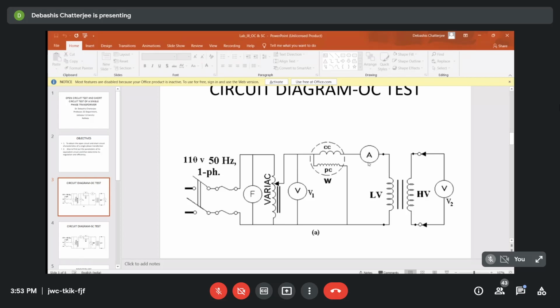So if you connect an ammeter, a reading of 50 milliampere can give you a larger error compared to 500 milliampere, because it needs some minimum deflection for better accuracy for all these instruments, whatever we use crudely in laboratories. Right? Now, this is one issue. Second issue is that the voltage of 1000 volt has to be there for rated voltage if high voltage was connected in the left hand side.